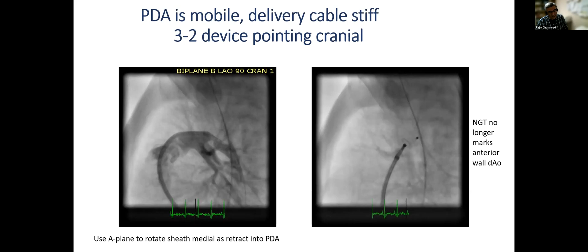And this is a recurring situation, and you have to be very careful with your landmarks with the echocardiography to confirm you're not obstructing the aorta. And in this particular patient, it required multiple passes and very careful use of the A plane and rotation of the sheath medially using the A-plane to confirm that the whole delivery system wasn't swinging to the left, and the device had to be partially extruded to anchor the delivery system in the duct, and then pulled in and then pushed out again in a kind of push-pull manner to retain the orientation of the duct.